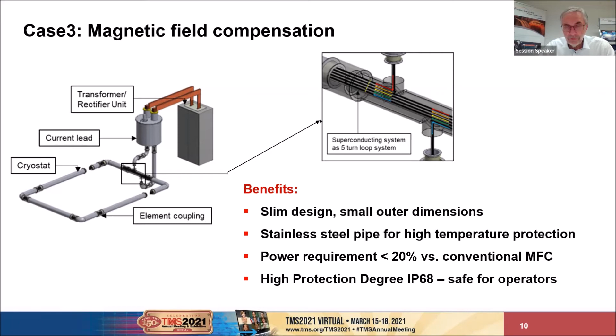If you want to connect to a nearby power source, let's say a wind park, solar plant, or a hydro plant, for upgrading your total power, there is a possibility to place the rectifier directly at the power source and to cross the distance by superconducting busbar system. This would avoid a two-step or three-step power conversion, with two transformers up to 110 kV in case you have a 400 MVA system.